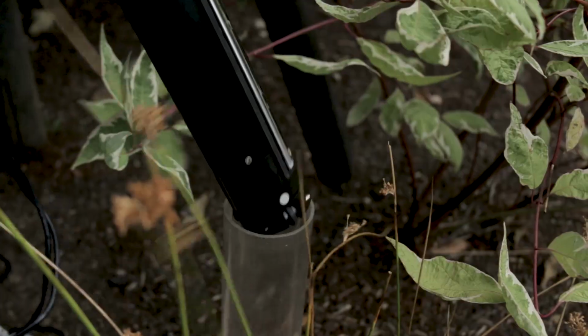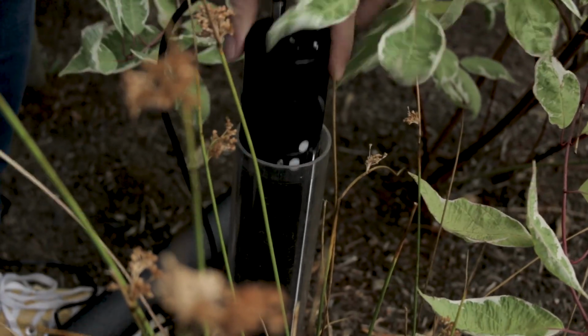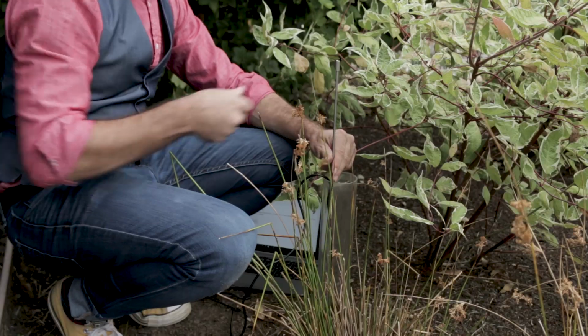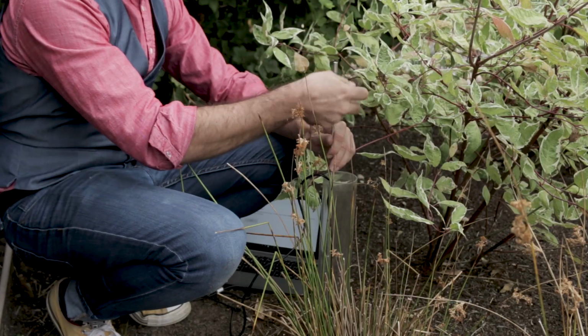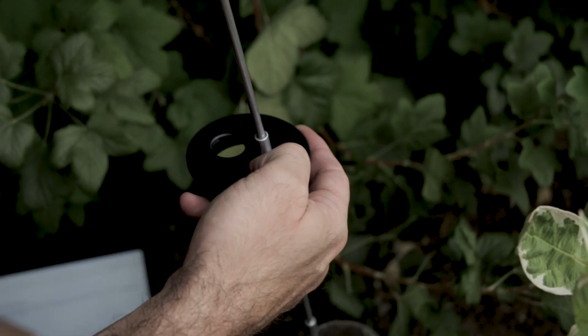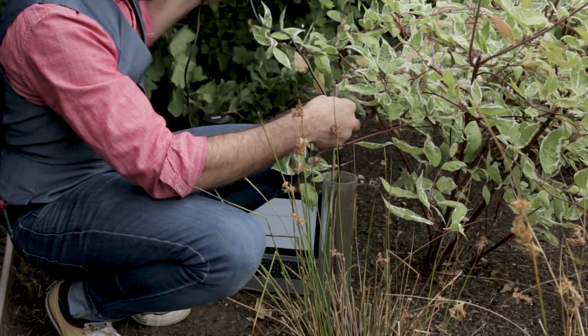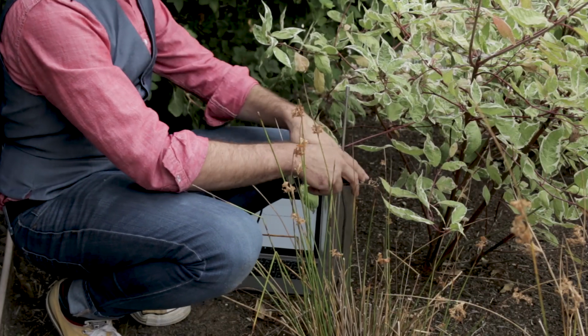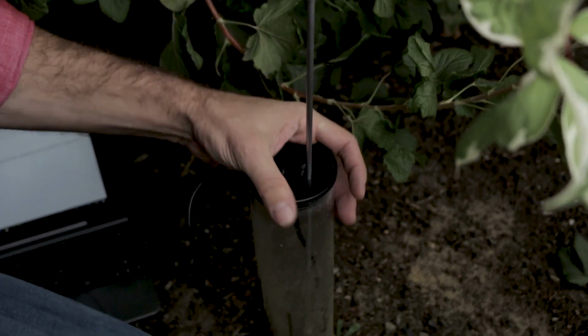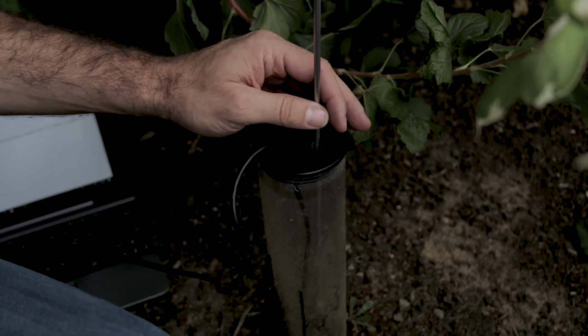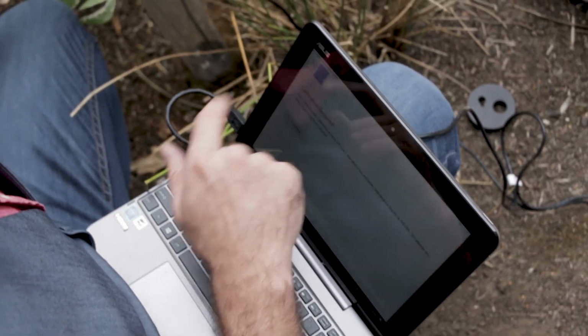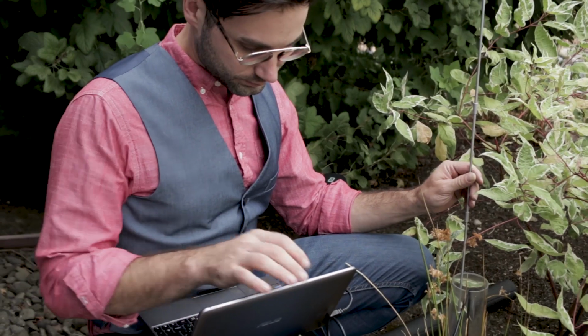Remove the insulating tube cap, insert the scanner, use the locking cap and indexing rod to both guide the instrument in a measured fashion, as well as keep out environmental factors. Scanning is as simple as pressing a button.